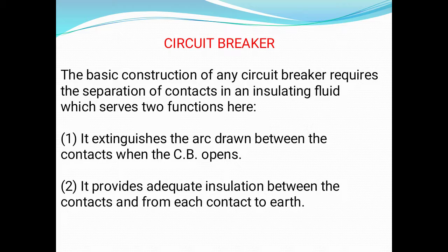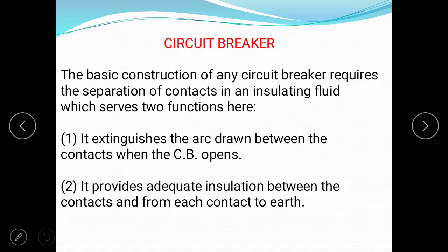So basic construction of any circuit breaker requires separation of contact in an insulating fluid. A insulating fluid serves two functions. First is it extinguishes the arc drawn between the contact when circuit breaker open. Second function is it provides adequate insulation between the contacts and from each contact to earth.